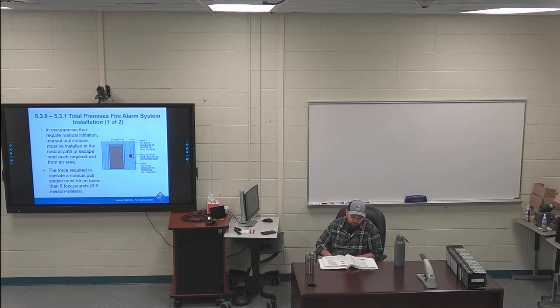You got different types of flame detectors. You got UV flame detectors. Wouldn't be a bad idea to read through where those are used or where they can be used. Nothing highlighted in UV flame detectors. IR flame detectors. Second bullet point. The second note for IR flame detectors on page 44 is highlighted. IR detectors cannot be used to detect alcohol, liquefied natural gas, hydrogen, or magnesium fires. Cannot use IR detectors for these.